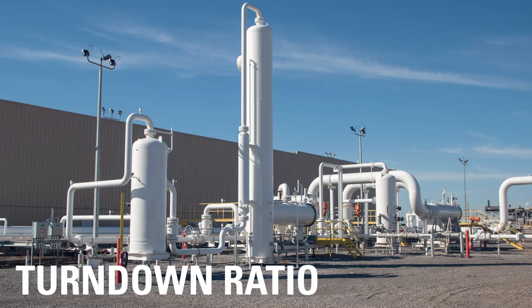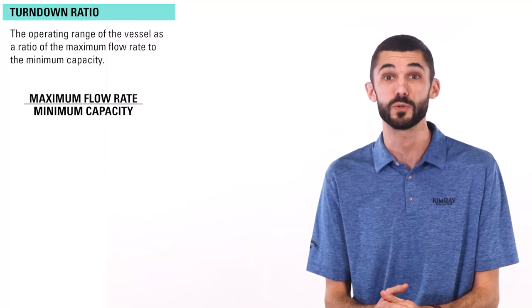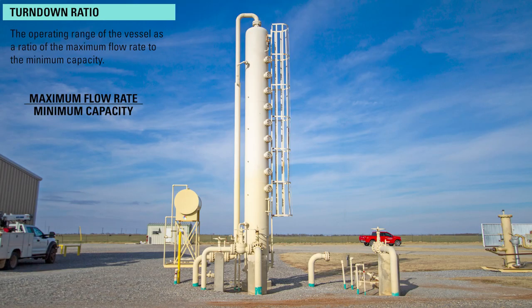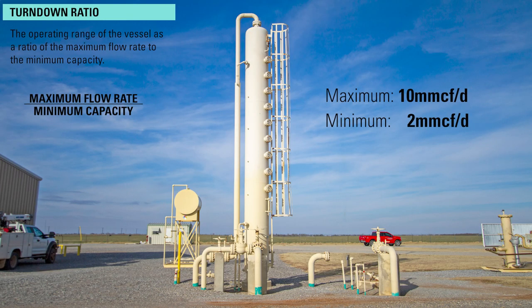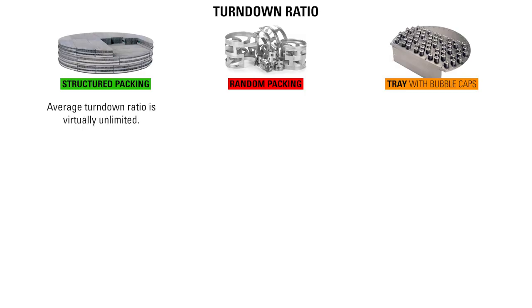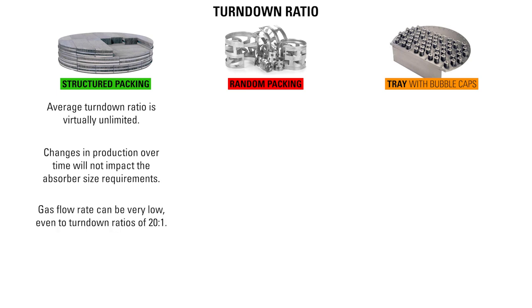The turndown ratio of an absorber is the operating range of the vessel as a ratio of maximum flow rate to minimum capacity. For example, if a tower is rated at a maximum of 10 million cubic feet per day and a minimum of 2 million cubic feet per day, the turndown ratio is 5 to 1. With structured packing, the average turndown ratio is virtually unlimited. Changes in production over time will not impact the absorber size requirements. As long as the glycol is fully coating the packing surface, the gas flow rate can be very low, even to turndown ratios of 20 to 1.